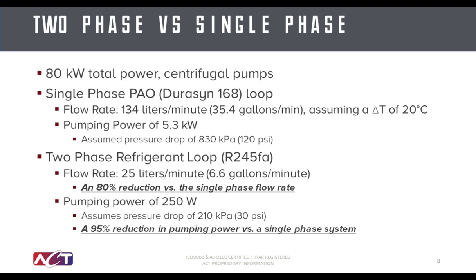Now let's compare two-phase systems to single-phase systems using some numbers. Let's assume an 80 kilowatt total power system. If you were to use a single-phase system using a typical cooling oil in the military industry, PAO, you would require 134 liters per minute, or 35.4 gallons per minute of flow rate, to achieve a temperature gradient across the plate of about 20 degrees C. That results in a pumping power of about 5.3 kilowatts.